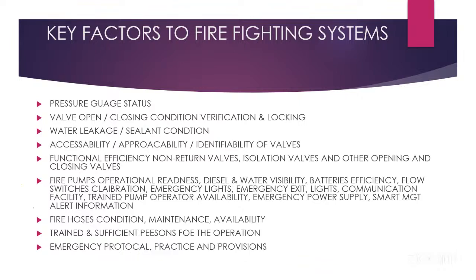So that is the pressure. The pressure gauge must be in the green level in the case of a fire extinguisher. In the case of a sprinkler system, which is based on the hydraulic system, what should be the maximum pressure? That should be at the remotest point. So the gauge must be fitted at the remote point so that you can understand the system pressure.